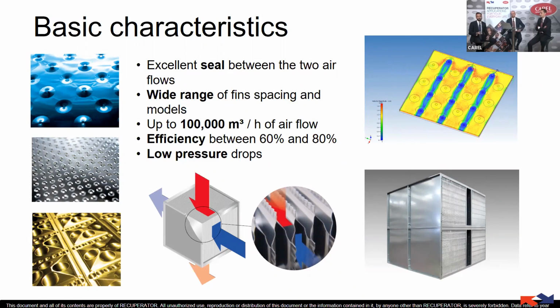We can have different sizes. We can use plate heat exchangers for hundreds of cubic meters per hour, even up to hundreds of thousands of cubic meters per hour, with efficiency from 60% up to 80–90%, keeping the pressure drop really low. The main characteristics are the geometry of the plate and the turbulence of the air, to keep the efficiency high and the pressure drop low.